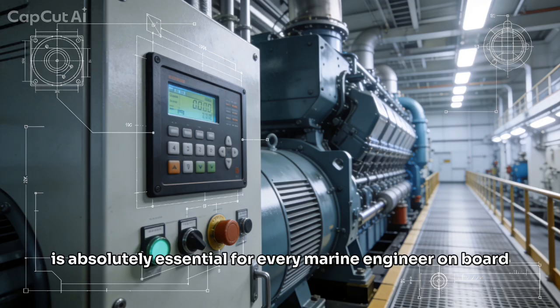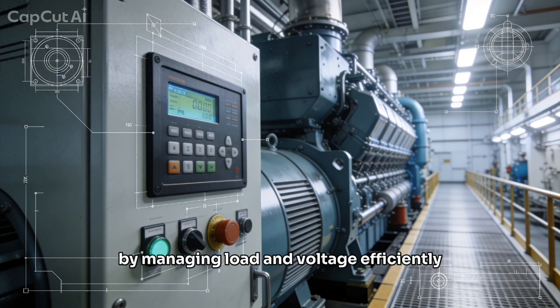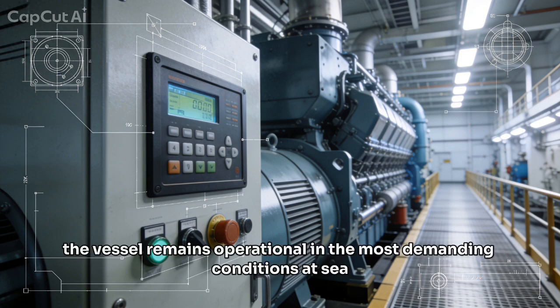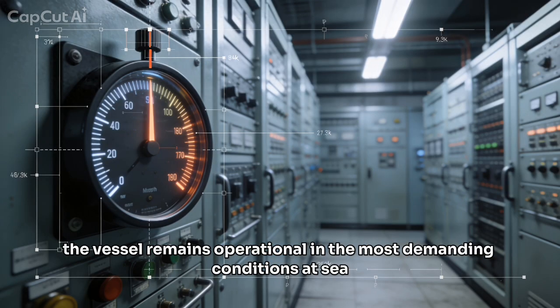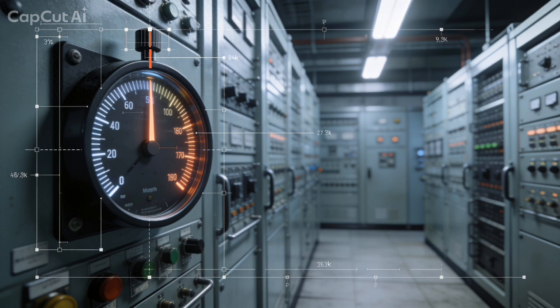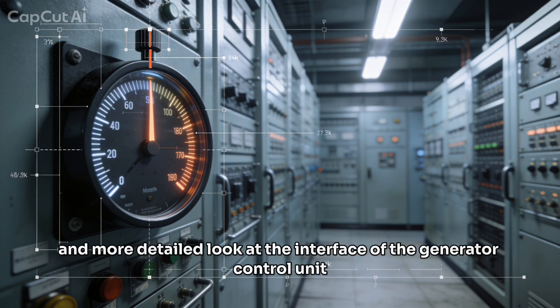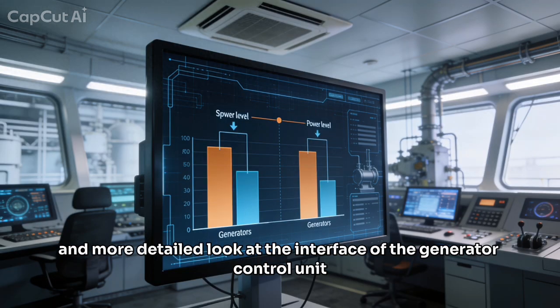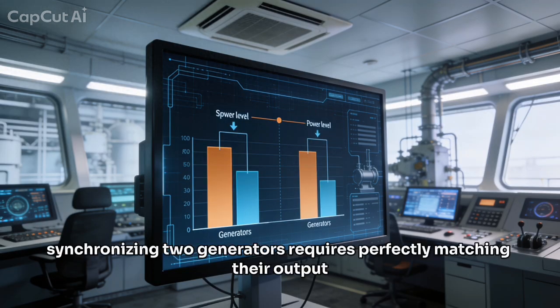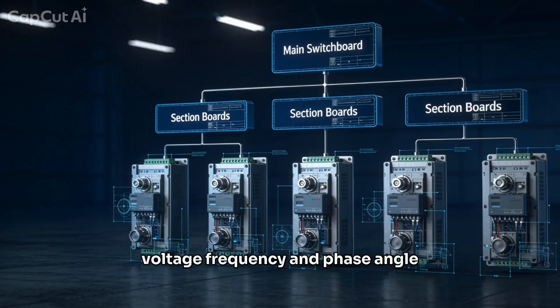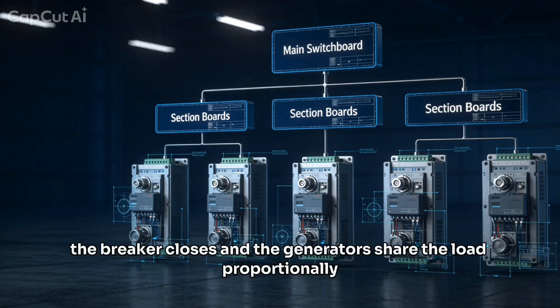Now let's take a much closer and more detailed look at the interface of the generator control unit. Successfully synchronizing 2 generators requires perfectly matching their output voltage, frequency, and phase angle. Once synchronized, the breaker closes, and the generators share the load proportionally. On the actual distribution side of the system, we have both primary and secondary distribution levels.